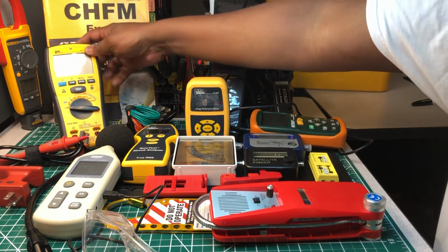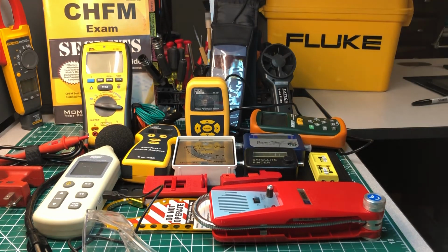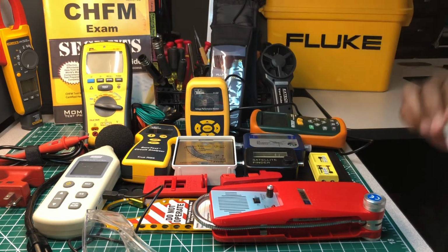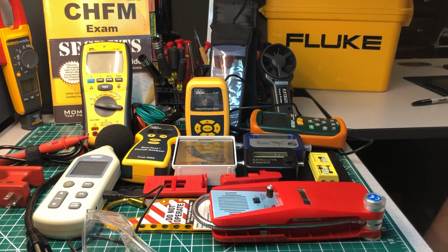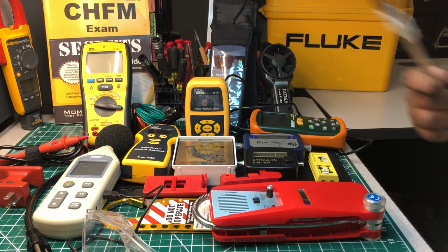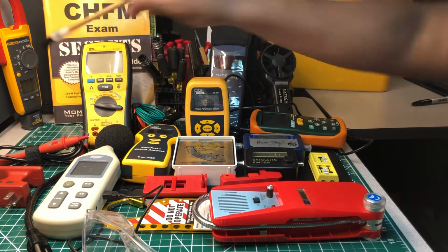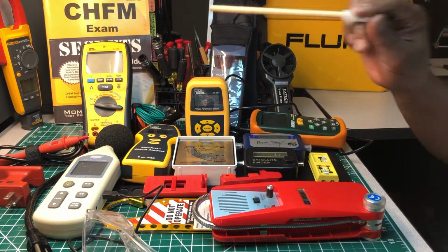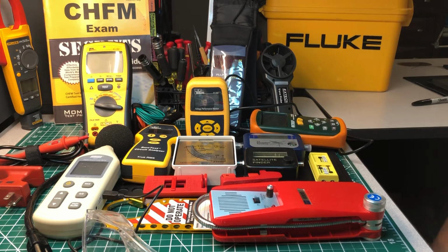Under the bottom here, a lot of you guys always ask me what that is. That's for stray voltage. If you're going anywhere where the power's off, and you want to test for stray voltage, that enables this meter to test for that. There's always a danger with stray voltage, even though the power may be off, because it may be laying next to a wire that may be hot and may carry that current, and that'll let you know if that wire has stray voltage on it or not. Anyway, that's the Fluke clamp.